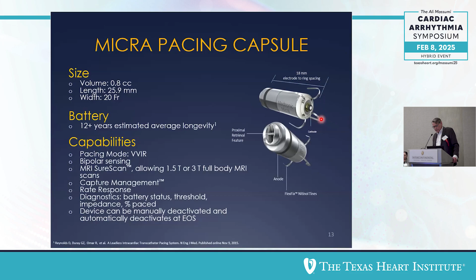It's MRI compatible. It's bipolar sensing and pacing. It has capture management, rate response. It has limited diagnostics. It will tell you about the battery, about the threshold. It'll tell you impedance. It'll tell you percent paced. But it doesn't give you too much in terms of diagnostics, because that chews up memory, and of course the battery is obviously small. You can turn it off, and it will turn off automatically when it reaches the end of service.